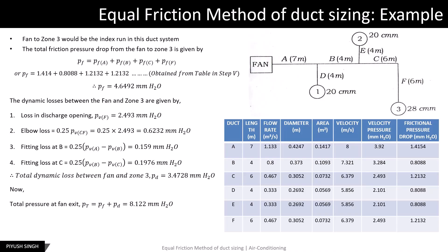The total pressure at fan exit is the sum of the frictional pressure drop in the index run plus the dynamic losses in the index run, which comes out to be 8.122 mm water. The static pressure at fan exit is the difference between the total pressure and the velocity pressure in duct A at the fan exit, which comes out to be 4.202 mm water.